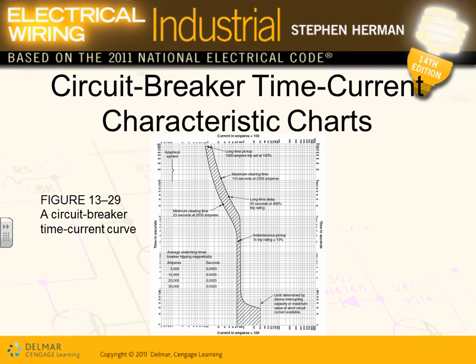You will be dealing 90% of the time with air. The air ones are called molded case circuit breakers, insulated case circuit breakers, as well as power circuit breakers, and medium voltage circuit breakers. The oil ones have a different type of design. The vacuum ones are typically for medium voltage and so forth. Any comments or questions about circuit breakers?